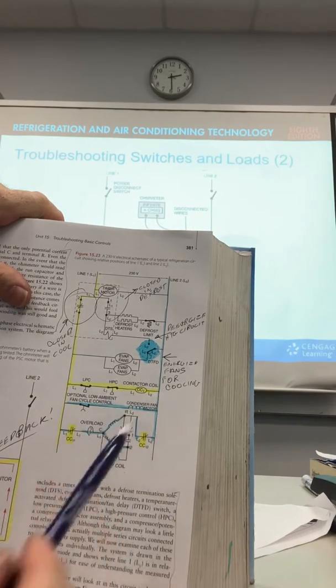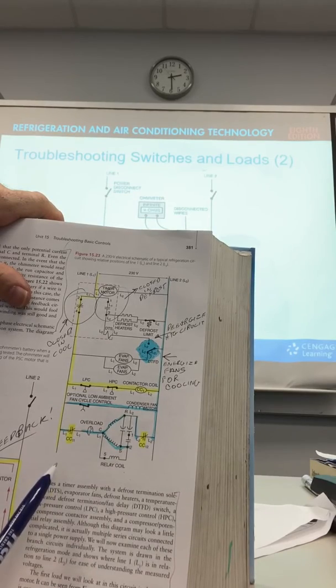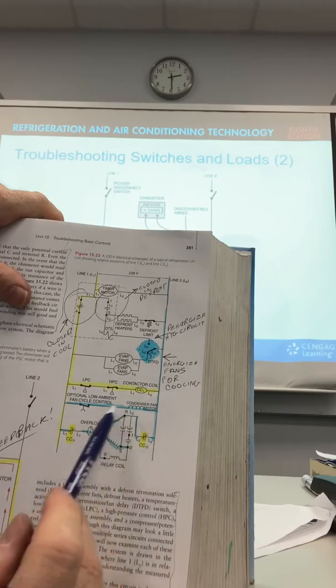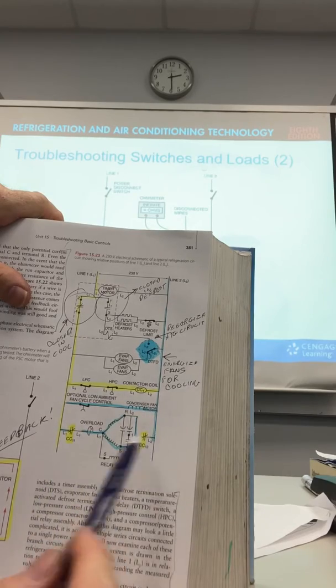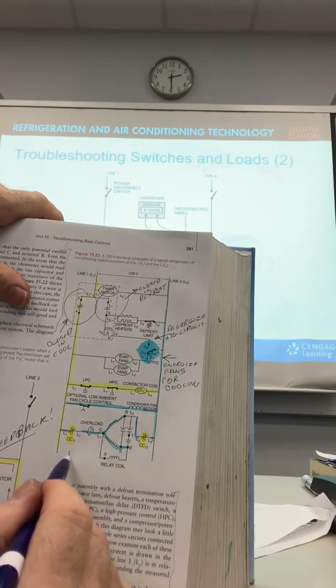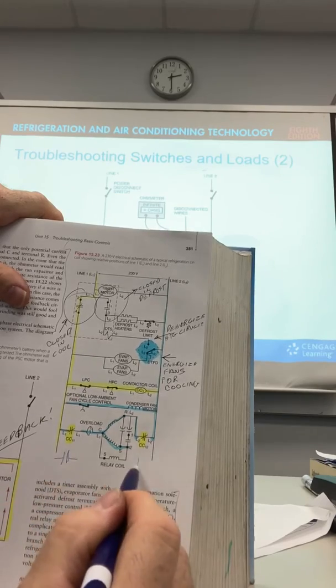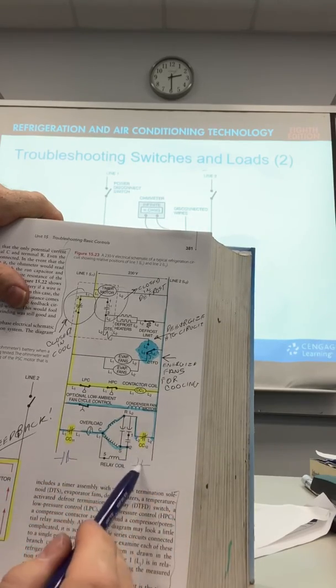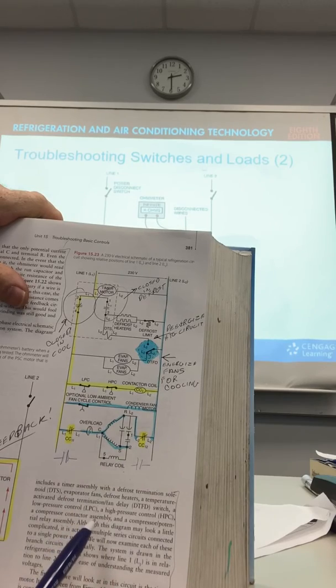And that does what? L1 and L2 open. That's L1 side of the contact and L2, and the compressor motor is taken out of circuit because those will look like this. And when those open, this is taken out of circuit.